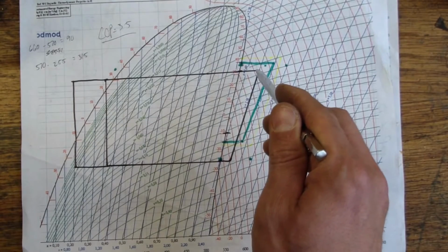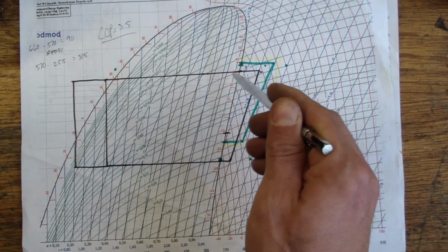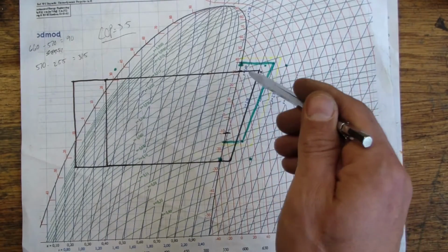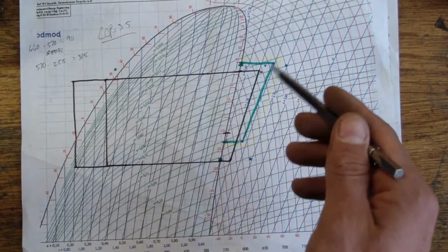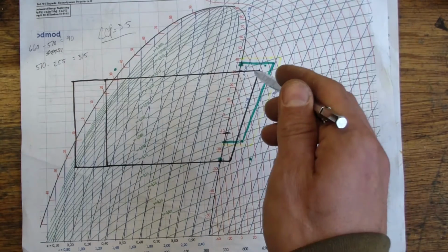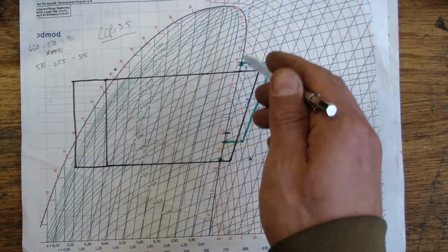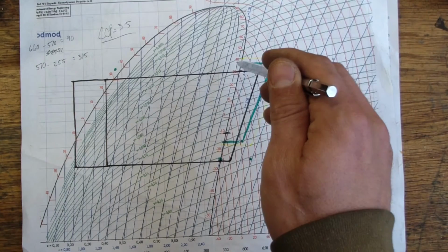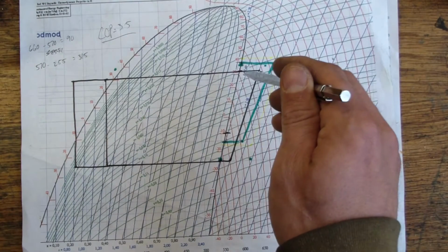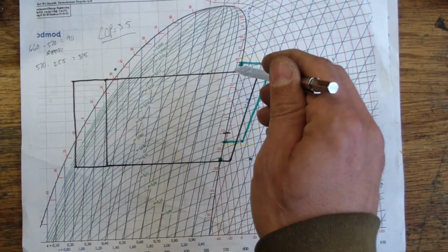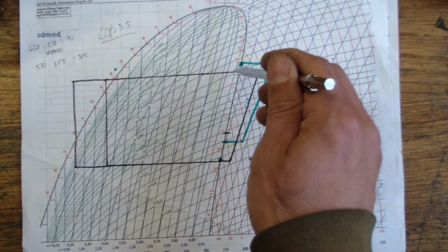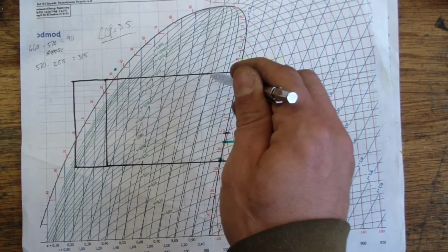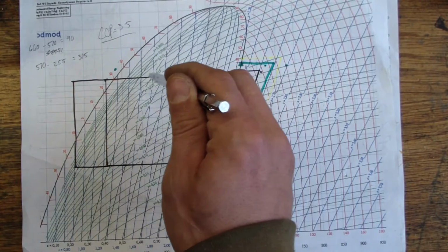As that higher temperature exists there than the ambient environment, it's discharging heat to the environment, warming the air around the condenser. Discharges all that superheat. We have a saturated vapor again, and as it continues to cool and to warm the environment around it, the enthalpy drops, and we start to get condensation. We get more and more liquid.